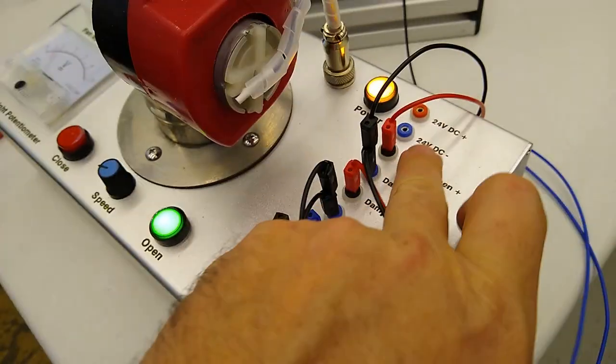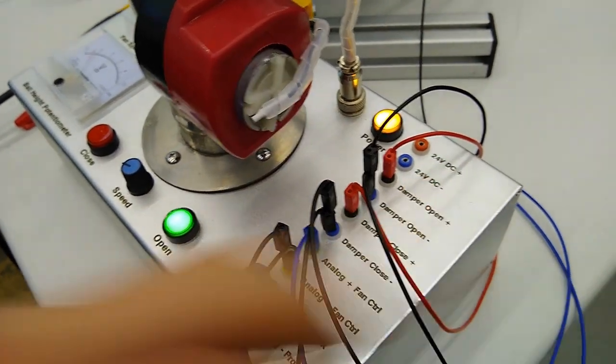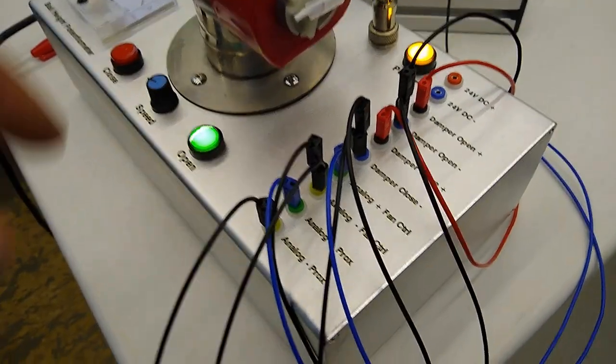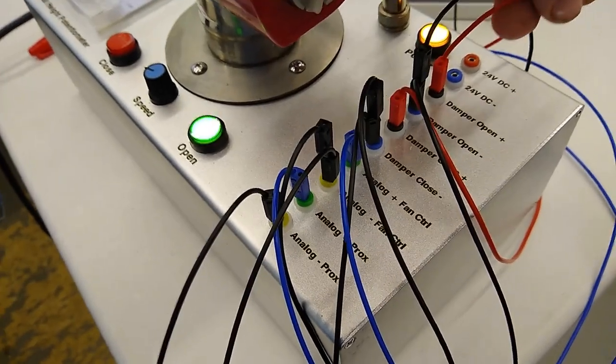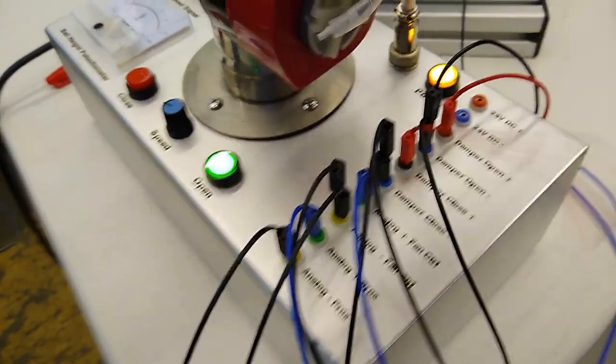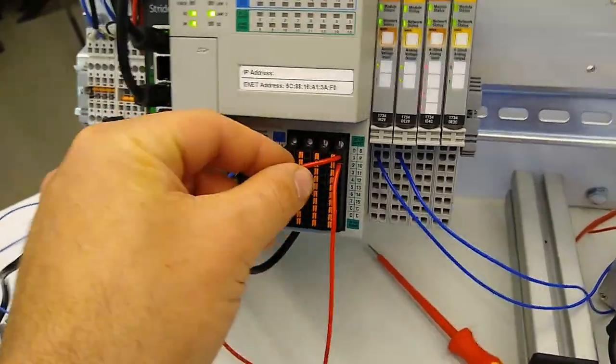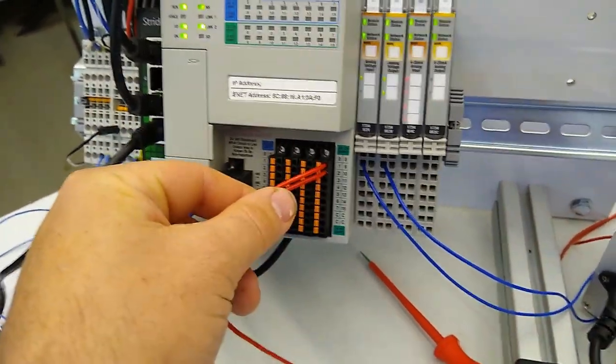Now if you wanted to have this completely separate it does have its own power supply built in. We're not actually using it and then we're going to have damper open and damper closed. These two wires here are going to go to discrete outputs on our CompactLogix PLC and we have them wired to number eight and number nine.